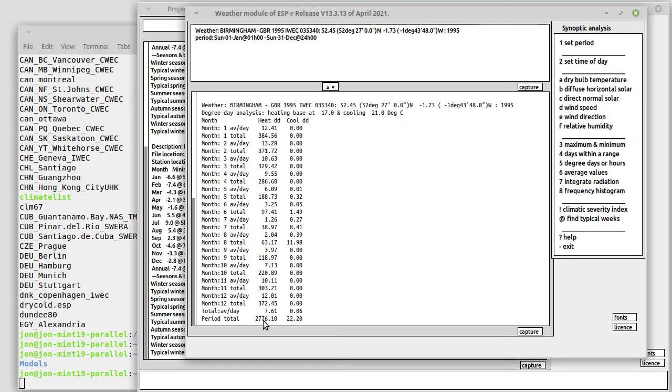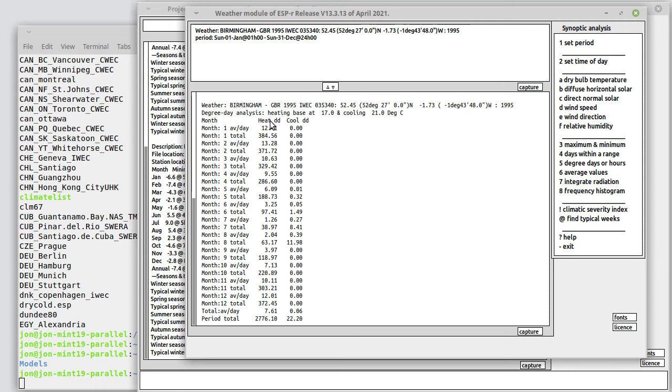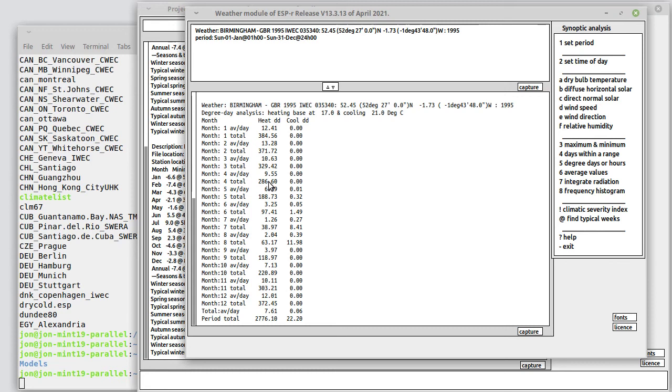We can see how those evolve over the year. 2,776 heating degree days over the entire year is a measure of its severity. We can see in that measure of severity that there is little difference between January and February. March is not much less severe, April starting to notice a change, May, and then June, July and August these numbers are very small.